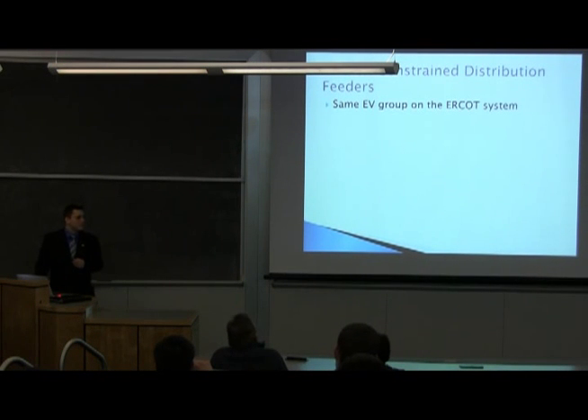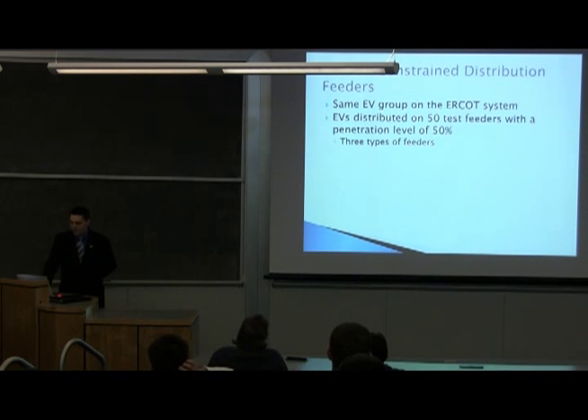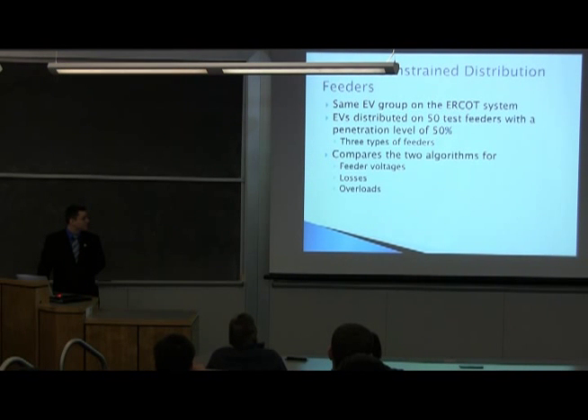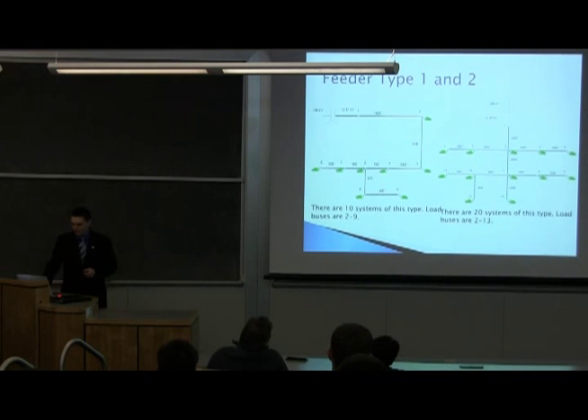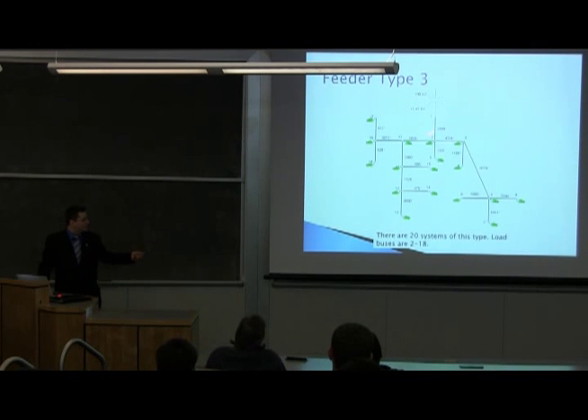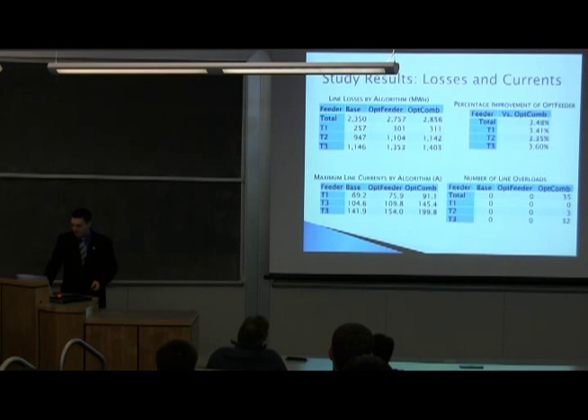So looking at the same group of electric cars on ERCOT, distributed amongst 50 different feeders of 3 different types, we looked at feeder voltages, losses, and line overloads to compare the two algorithms. We had one feeder type that looked like this, another that looked like that, with EV loads distributed at all the little EV points, and our final feeder was much bigger, looking like that.